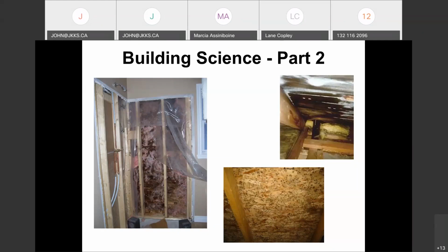The image to the left with the bathroom and the shower area, those are two little electric heaters trying to dry out this wall. A good attempt, but we can see again what we talked about in part 1, about the main principles. We're talking about moisture and air movement in and out of the building envelope, that outer, we'll call it, layer of the building. The dew point occurring inside the wall, in this case an exterior wall. We can see the window off to the right-hand side with, again, the photo to the left.